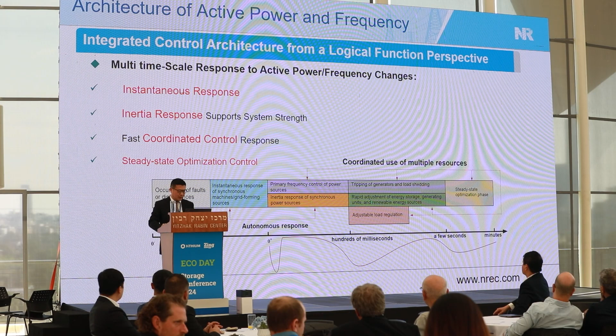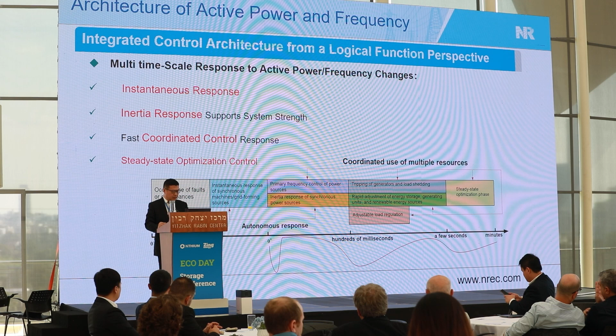This slide lists the architecture of active power and frequency response. When an emergency happens, there should be a multiple time-scale response to support voltage and frequency - an instantaneous response, an inertia response to support system strength, fast coordination control, and steady-state optimization control.